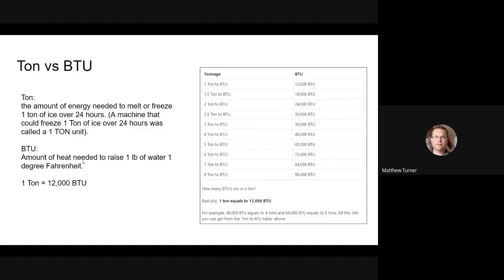BTU is the amount of heat needed to raise 1 pound of water by 1 degree Fahrenheit. 1 ton equals 12,000 BTUs, and that's linear, so 2 tons equals 24,000 BTUs, and 1.5 tons equals 18,000 BTUs. If you remember that 1 ton is 12,000 BTUs, and the nameplate lists the BTUs, you can convert that to tons if you need to report tonnage, or vice versa if the model number shows tons, you can convert to BTUs pretty easily.